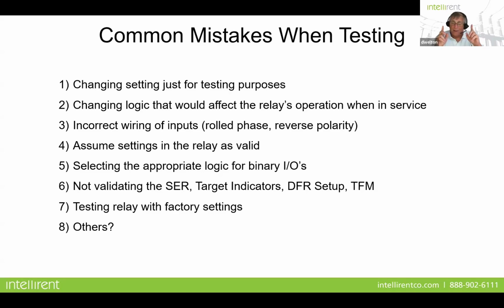And another one, don't test a relay with factory settings. That just doesn't make sense. Even if you're just doing kind of an assessment test on a new relay that you're thinking on standardizing it, don't test the factory settings. Put real live settings in that would actually apply to where the relay is going to be installed. Okay, there are others. If you can think of others, certainly just let me know. But these are the most common ones that I see during the testing process.